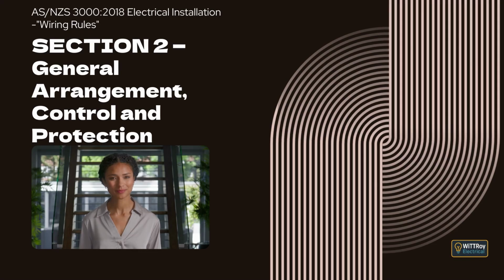2.3.2.2.2 Identification. This clause explains that all isolation devices must be clearly identified so people know which circuit or equipment they isolate. Identification can be by marking or, when isolating one item, by placing the device where it is obvious. A switch that displays the recognized isolation symbol from the relevant product standard is considered suitable for isolation. The standard also lists the product standards that apply to isolation devices.